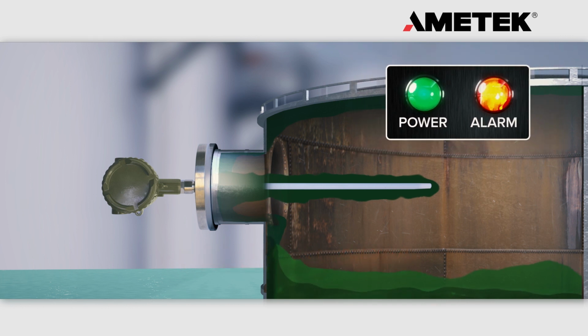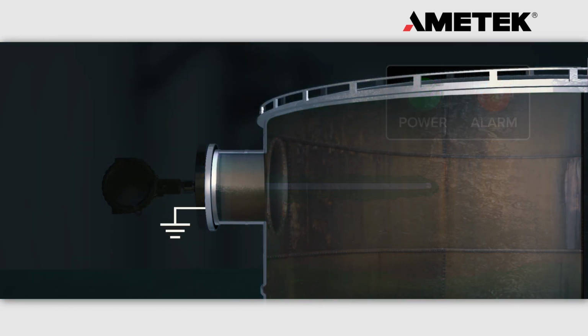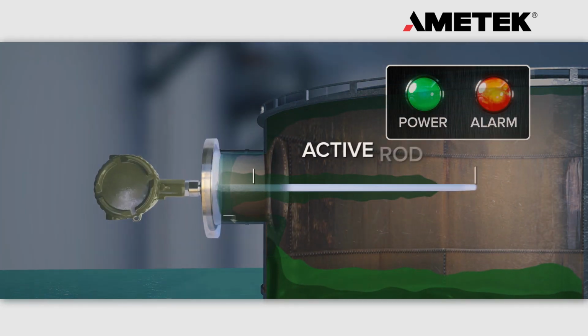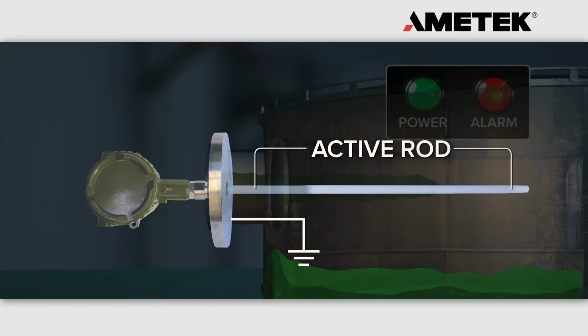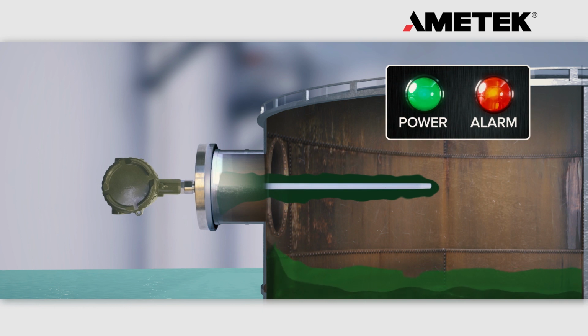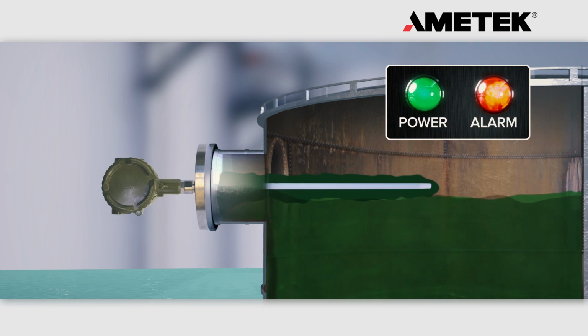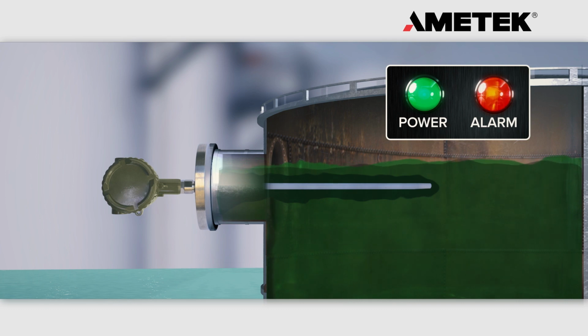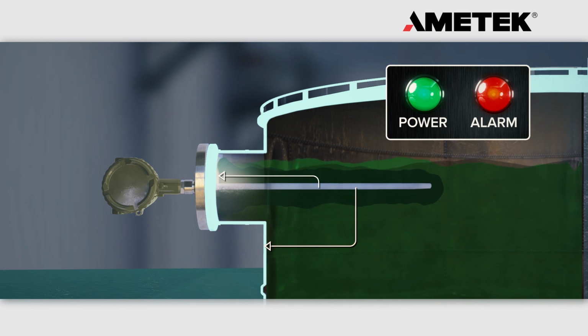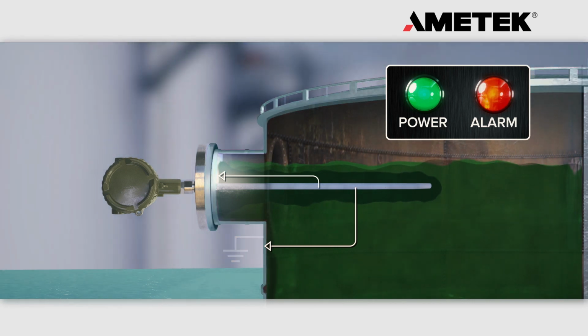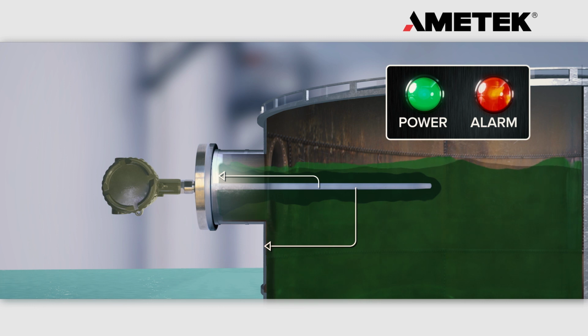Traditional capacitance probes are two-terminal style probes. They're called two-terminal because they consist of two electrical elements, ground and an active rod. When using this type of probe in a conductive product, the process media rises and touches the probe. This contact completes a conductive path from the active rod to the metallic tank wall, allowing current to flow from the probe to ground. This current flow is detected by the electronics and an alarm is generated.